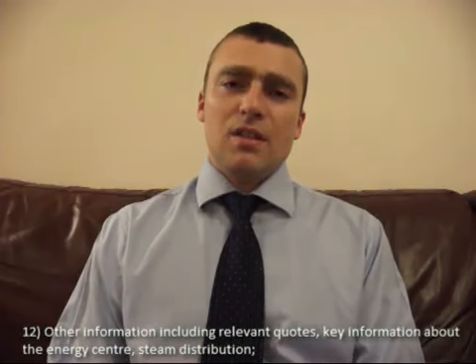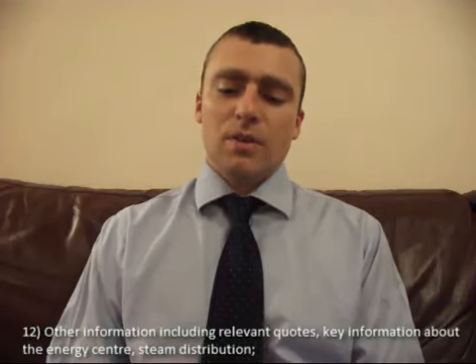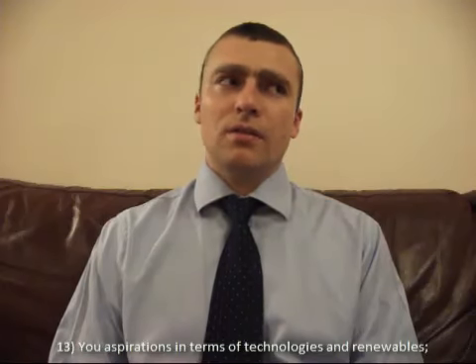If you've got a steam system, a little description about the steam system, about the energy center, percentage of condensate returned, if you have any steam processes. What are your aspirations in terms of the technologies? Do you want renewables? Every time I ask these questions, they say, yeah, we want, but you've got to be realistic. Those technologies have a very long payback, and you've got to think: do I do solar thermal on the roof, or do I upgrade the BMS in 2 buildings? The savings will not come from your solar thermal, the savings will come from the BMS. So think about it carefully.